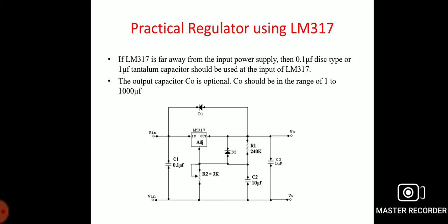When the filter capacitor is used, it is necessary to use protective diodes, so these diodes do not allow the capacitor C2 to discharge through the low current point of the regulator. These diodes are required only for output voltages above 25 volts and for output capacitance values of 25 microfarads and above.